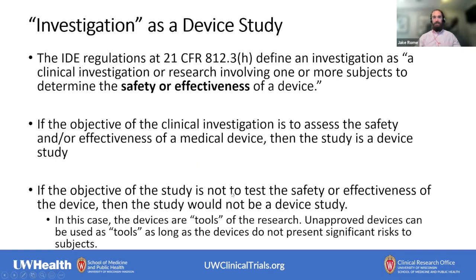In that case, as described here, you're using the device as a tool. So for the most part, if you're using an investigational device and you're not evaluating it for safety and effectiveness, and that device does not present significant risk to subjects, then you're going to fall outside of the scope of the IDE regulations, and you would be able to utilize that device even if it is an investigational.